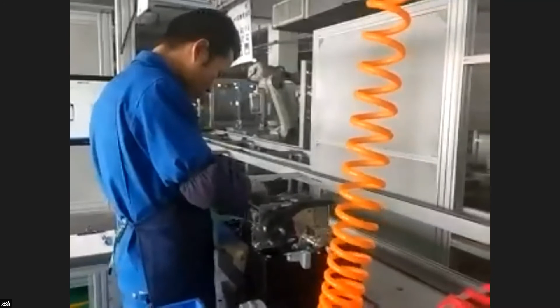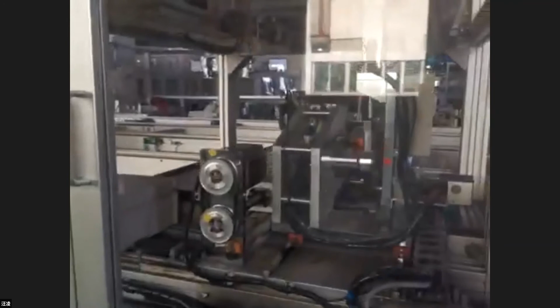After the controller is fixed and installed, we need to test the trip force, because trip force is very important. They test it more than 10 times, on and off, letting it trip and recording the force of the trip. The trip force range is limited - minimum is 4, maximum is 9.